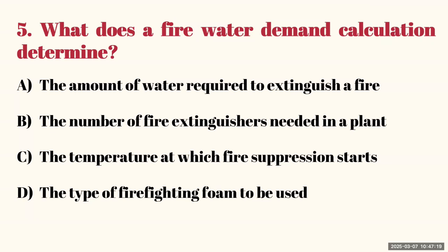There's a lot of studies done in the industry for fire water specifically. For example, in our fire water calculation report, we find the total water needed, the volume of storage tanks to contain this water, and the time this water can last. The standard says that you need at least storage that can maintain 2 hours of extinguishing, which is a rule of thumb from the industry, but of course it changes based on the plant, the process, and a lot of other factors.